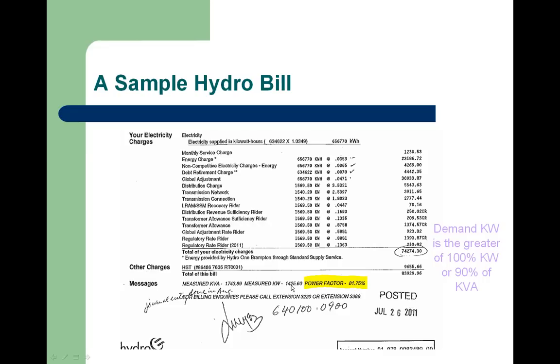And if you were to take the kilowatt demand of 1425.60 and divide that by the kVA of 1743, you would get a power factor of 81%. So in this particular case, our power factor is less than 90%. So the utility will take the measured kVA, which is 1743, and take 90% of that. If we look up into this area here, we see a demand of 1,569 kilowatts, that basically is 90% of the peak kVA.